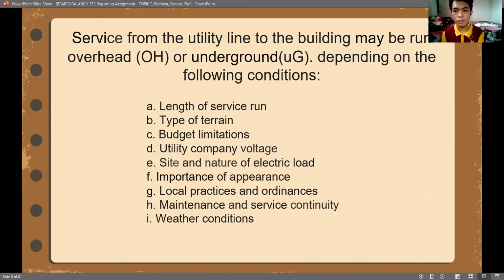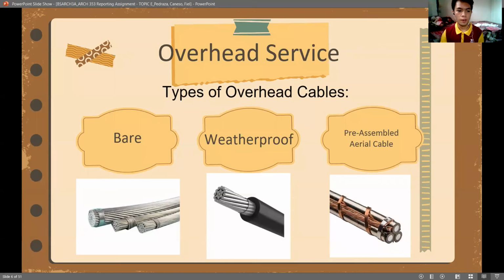Service from the utility line to the building may be run overhead or underground, depending on the following conditions. Here are the conditions: length of service run, type of terrain, budget limitation, utility company voltage, size and nature of electric load, importance of appearance, local practice and ordinances, maintenance and service continuity, and weather condition. So here is the overhead service. Overhead service depends on terrain and other factors. The cost of overhead as compared to the underground installation is in the range of 10% to 50%.